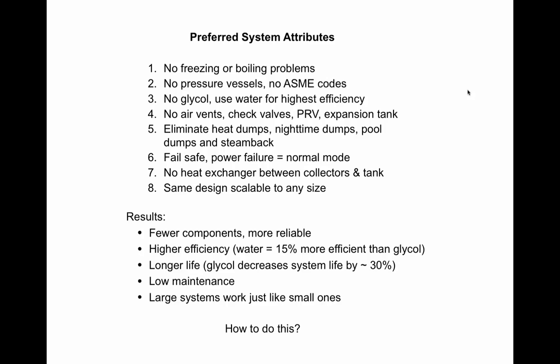If we could eliminate the need for any kind of heat dump — nighttime dumps, pool dumps, steam backs — we would eliminate a lot of auxiliary equipment, controls, and pumps. Remember, all of that stuff fails when the power fails, so the best heat dump in the world is useless if you have a power failure. That brings up point number six: power failure.